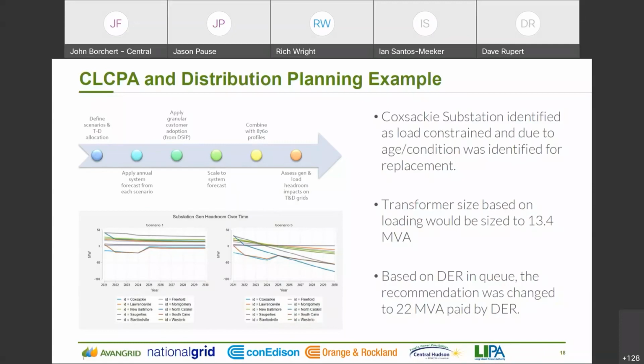The planning process recognized that it was much less expensive to increase the transformer size than to add an additional transformer or change the transformer later. In this instance, which was done prior to the cost share 2.0 process that is in place today, the DER developer paid the nominal amount for a larger transformer to help interconnect in the future and improve hosting capacity at the Coxsackie substation.